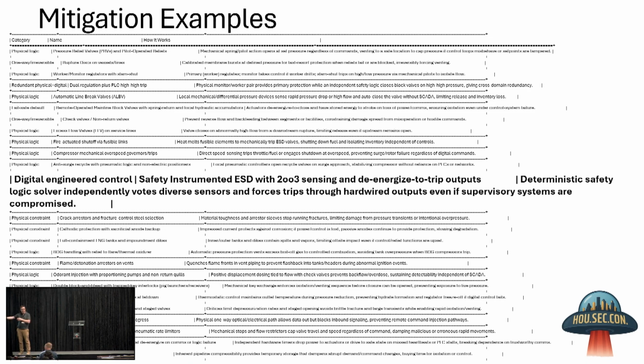So if a sensor has been compromised and it's delivering false data, or someone has inserted themselves in the middle of that channel and is manipulating that information, that sensor is no longer trustworthy. From a safety solution standpoint, I might be able to catch that by using that voting mechanism to either discredit that sensor, so I'm not going to use it in the calculation, or more than that, I can cause the result to de-energize the trip outputs.